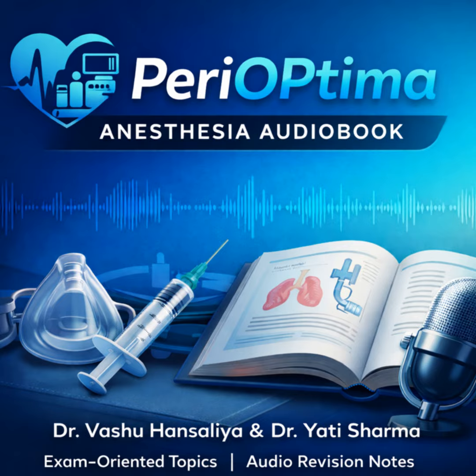Very efficient. When you squeeze the bag, the positive pressure pushes the expired gas down the long tubing towards the remote APL valve. The continuous FGF at the patient end acts as that piston we talked about, efficiently pushing the exhaled gas out. And the FGF requirements for that? Efficient. FGF is about 1 to 2 times the minute ventilation. It's less efficient than Mapleson A for spontaneous breathing, though.